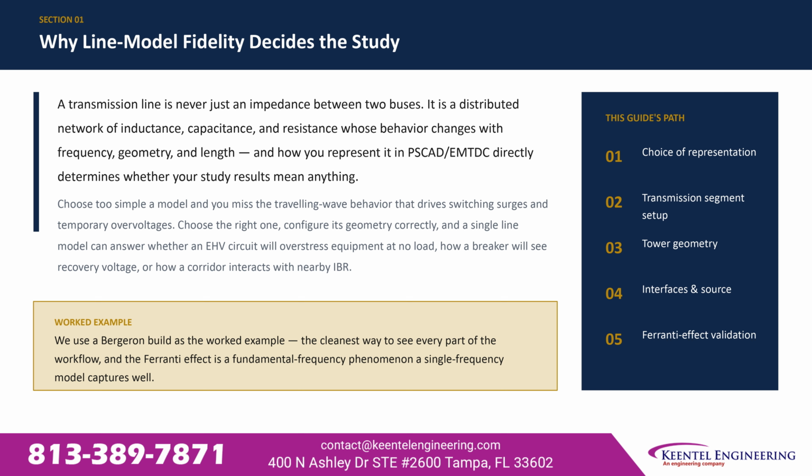A transmission line is never just an impedance between two buses. It is a distributed network of inductance, capacitance, and resistance whose behavior changes with frequency, geometry, and length. And how you represent it in PSCAD determines whether your results are meaningful. Choose too simple a model, and you miss the traveling wave behavior behind switching surges and temporary overvoltages.